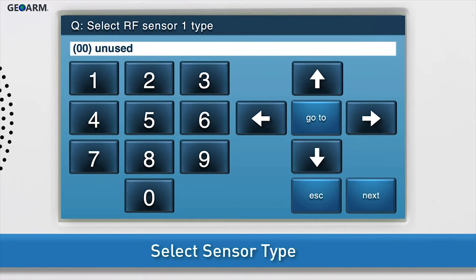Select the sensor type. There are two ways to change the sensor type. Option 1: Press the right arrow to scroll through the various sensor types. Option 2: Use the on-screen keypad to type in the two-digit code for the desired sensor type. Select the sensor type that corresponds to the hard-wired device you are converting.